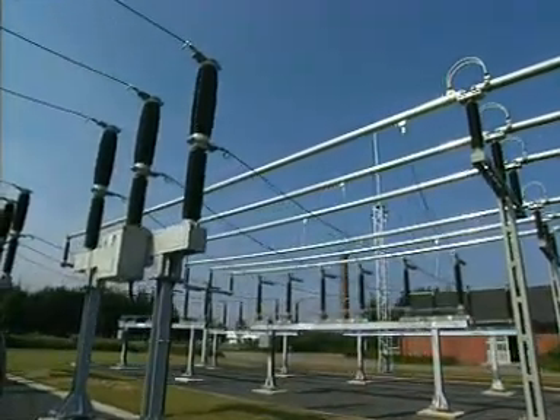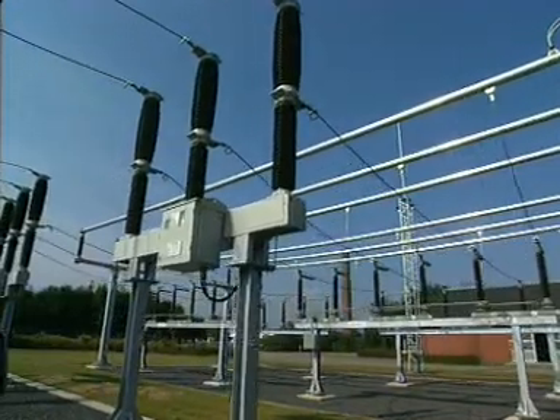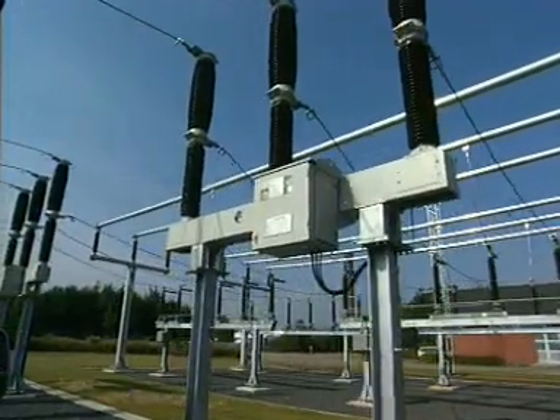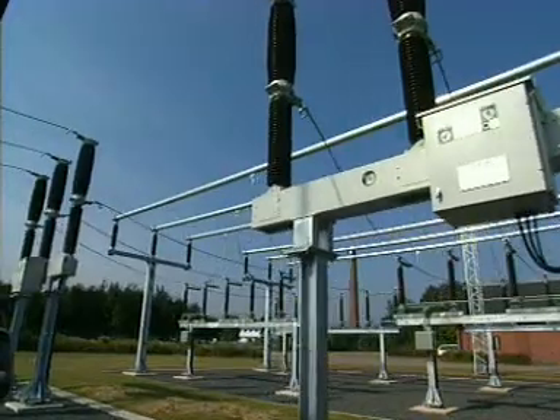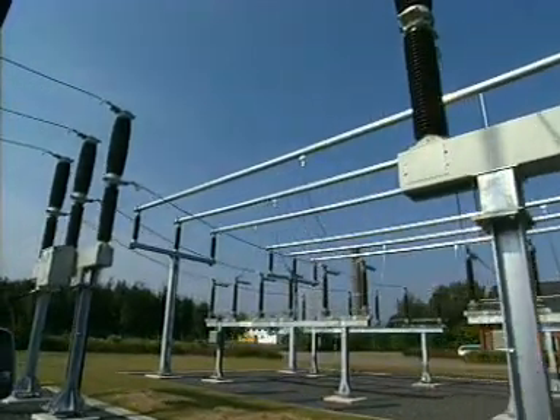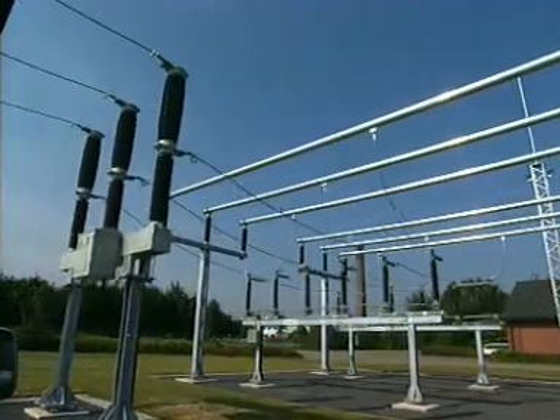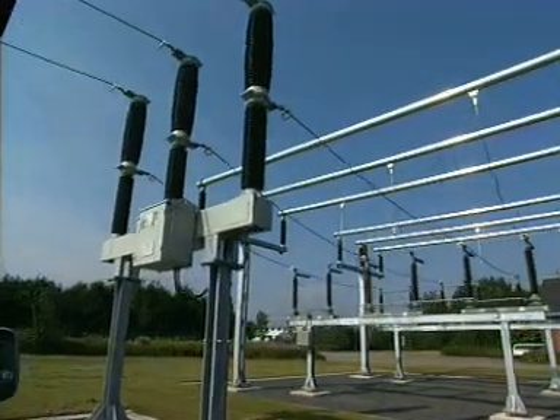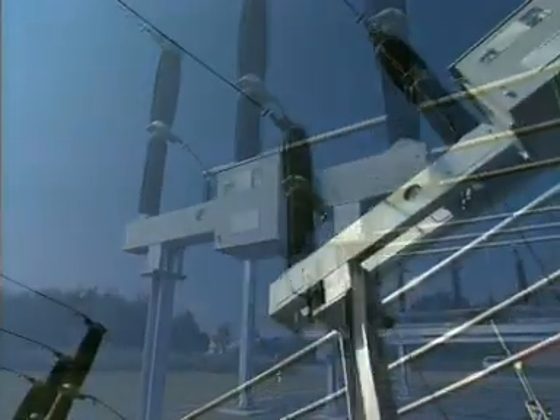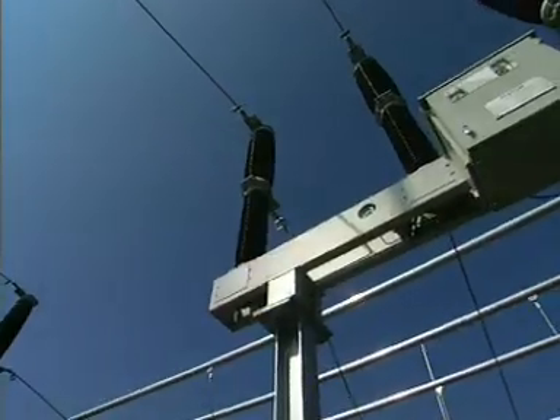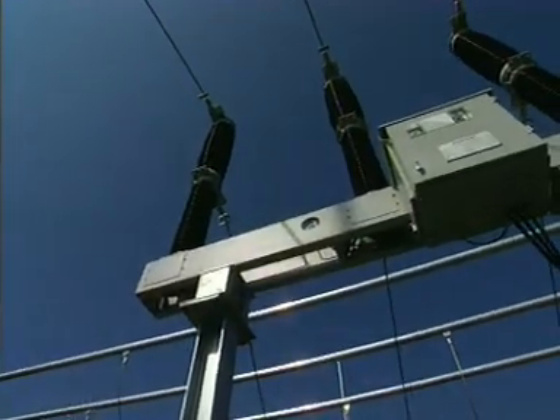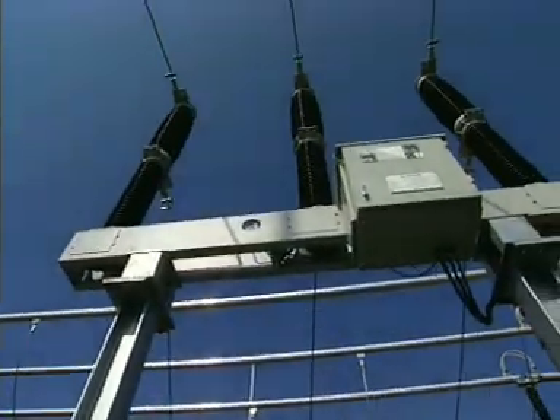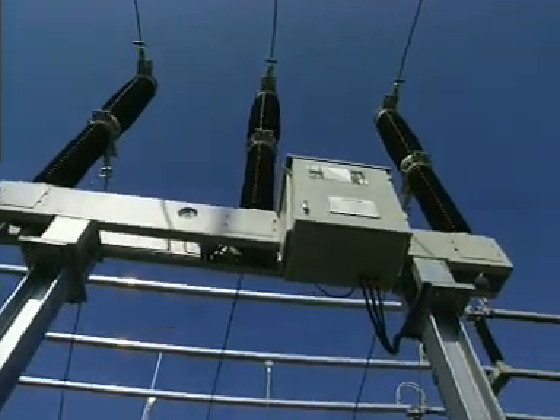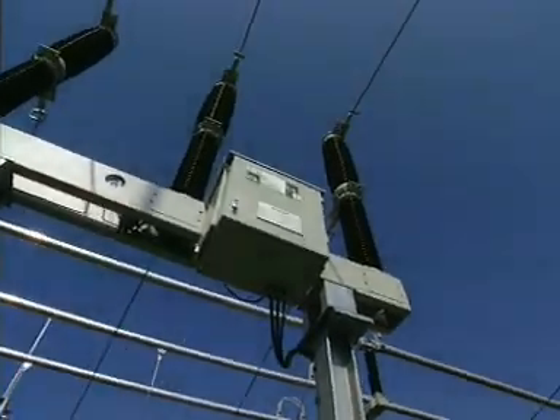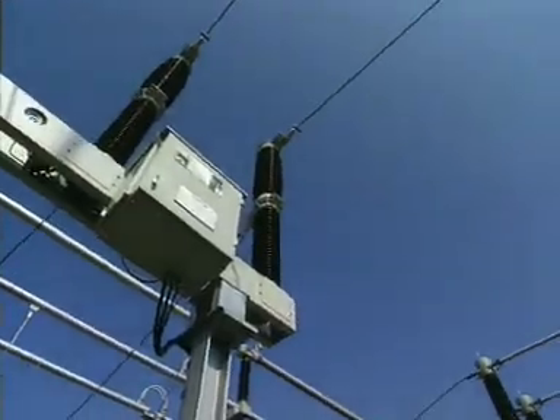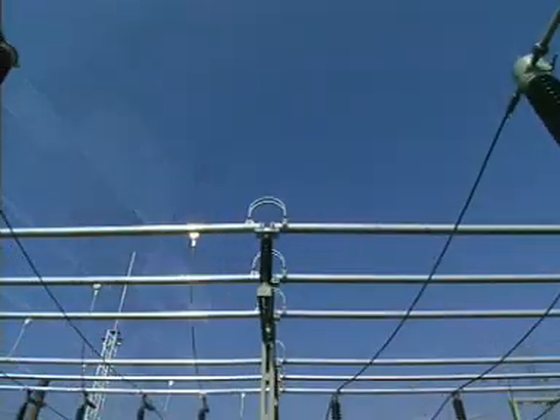This film is designed to complement the operating manual for the SF6 circuit breakers GL311 and GL312. It describes the basic reconditioning and recommissioning procedures. Please consult the operating manual supplied with the equipment for safety instructions, measured values, tightening torques and other detailed information. In particular, please note that improper handling of the porcelains can result in personal injury or property damage.